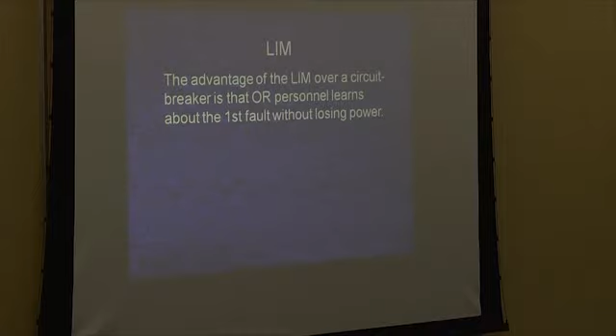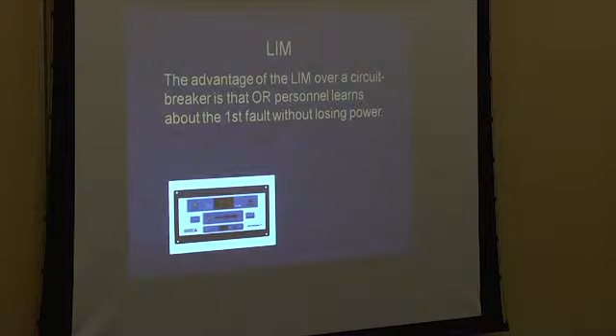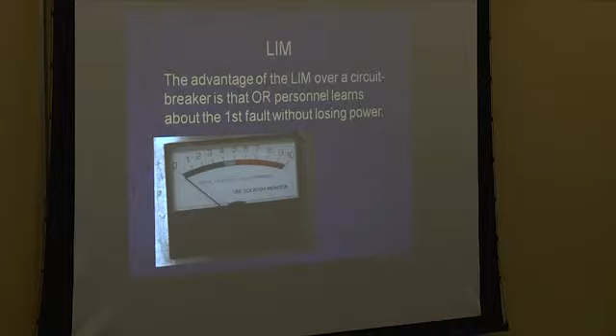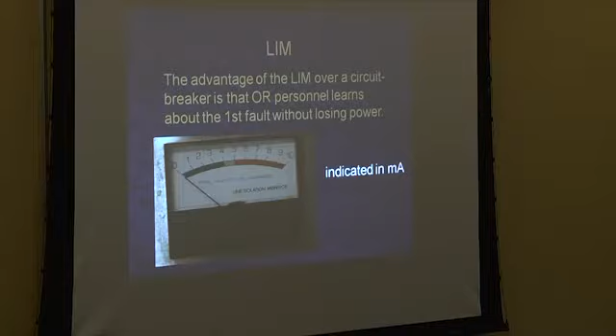How about that line isolation monitor? Well, the advantage over the circuit breaker, as we said, is it doesn't make you lose power. Here's an old system — it tells you how much electricity is leaking, and it has an alarm system which will make a lot of noise.